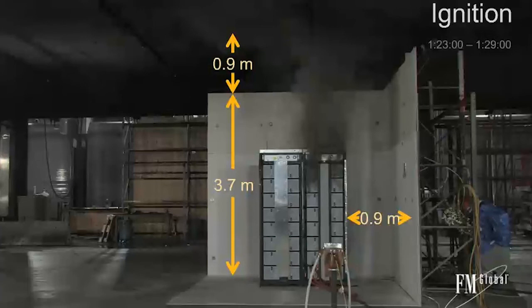And because it's a sprinkler test, sprinklers operate when they get hot. If you can picture an energy storage system in a storage closet, all of the heat from that fire is going to go right up and be captured at the ceiling level, and the sprinkler is going to operate quickly because it heated up quickly. If you were to put that same energy storage system into a very large room, now you have a lot of dissipation of the ceiling gas flow that's going to allow the sprinklers to heat up slower, and so the fire is going to be larger when the sprinklers operate. That's a condition I want to have, because once I know I can protect that slow response to the sprinkler, I should be able to apply the results to a smaller room.